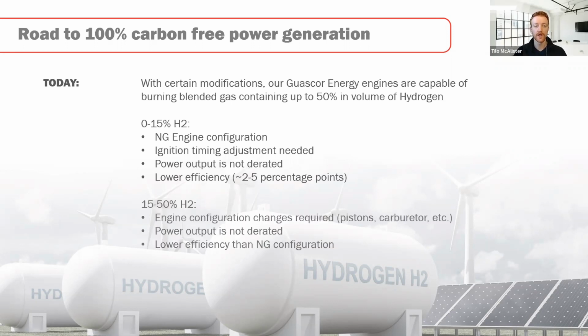Now, if we want to go up to 50% hydrogen, we do a couple of additional hardware changes to the same engines, done as a retrofit. 90 to 95% of the equipment is unchanged, but we'll put in different pistons, a different carburetor, a couple of component swaps, plus controls changes. Then we can run on 50% hydrogen without derating the power, so we can still get a megawatt of electricity out of the same footprint, which is important for the goals of this project.